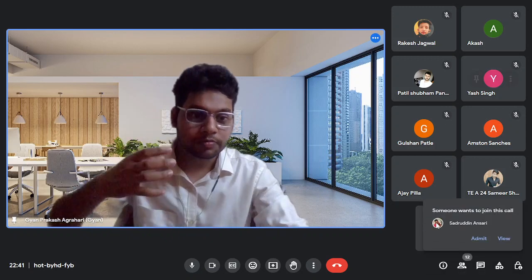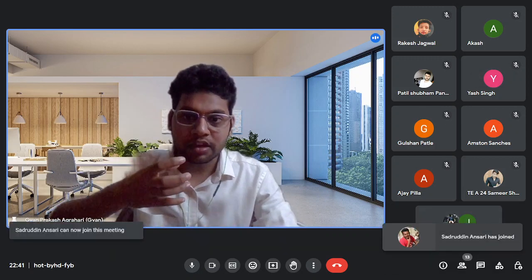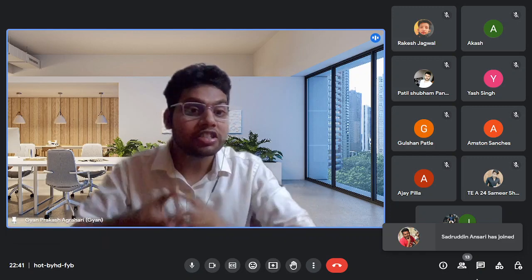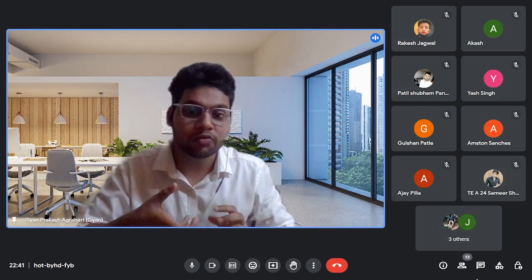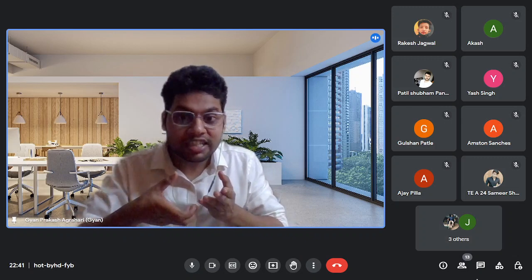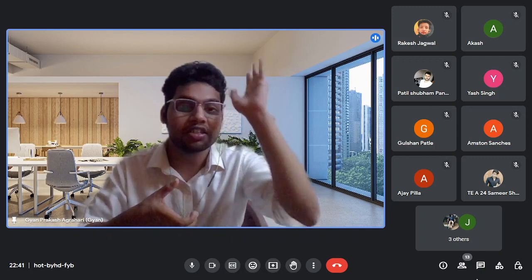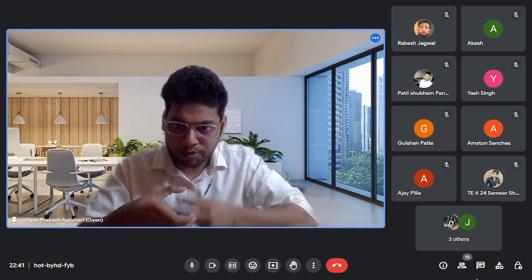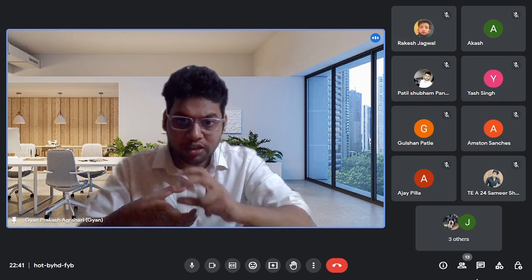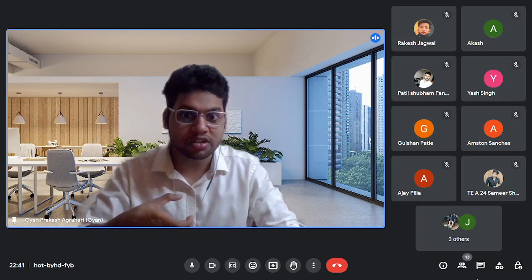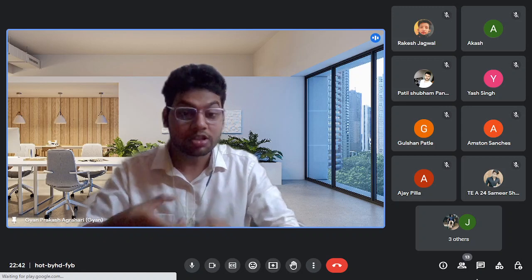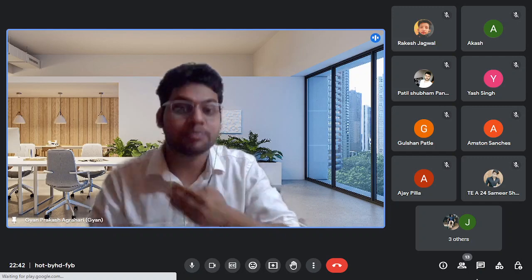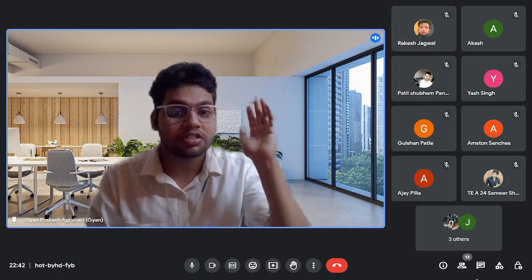So consider here, this is the eye of the impeller. When the impeller is rotating, it will exert centrifugal force radially toward the discharge side of the volute casing, and due to which the fluid gets displaced radially toward the discharge side of the volute casing. When the fluid is displaced, it will create a vacuum space at the eye of the impeller, like here. And that vacuum, that void space, is the negative pressure region, the low pressure region. This is how negative pressure is created, guys. It is because of centrifugal force, the fluid is displacing radially toward the discharge side of the volute casing.